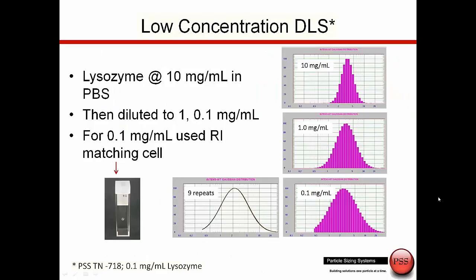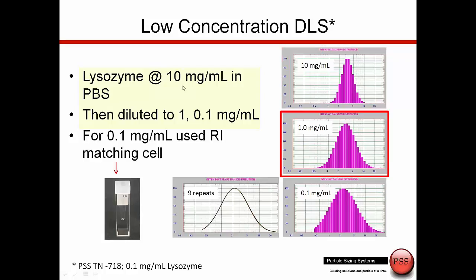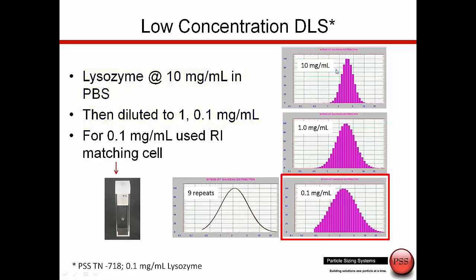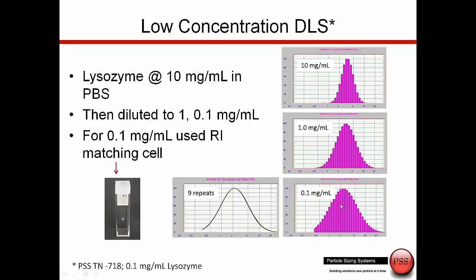I recently put out a technical note showing off the low-level concentration abilities of the NICOMP. I was taking lysozyme, which is a protein with a known size near 3.5 nanometers, and mixed it up at 10 mg/mL, then diluted to 1 mg/mL and down to 0.1 mg/mL. This showed how we get the same size — with a little broadening — and the ability to measure at very low concentrations for this very small, weak-scattering protein.